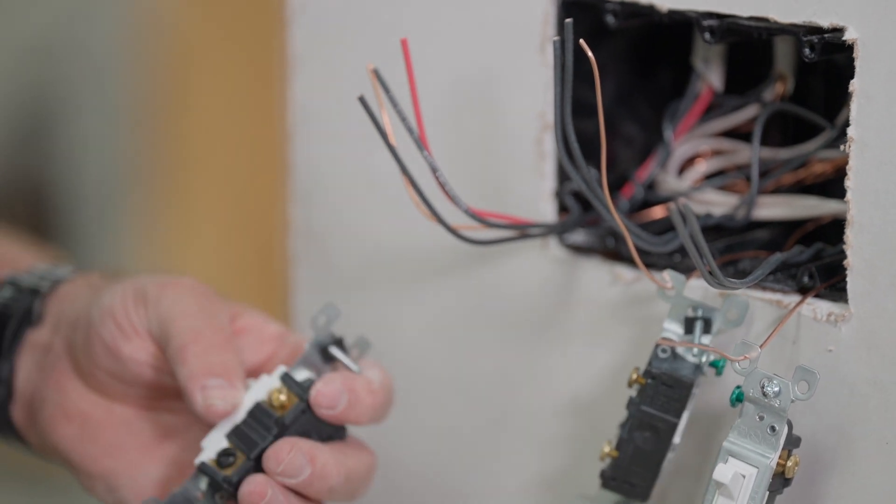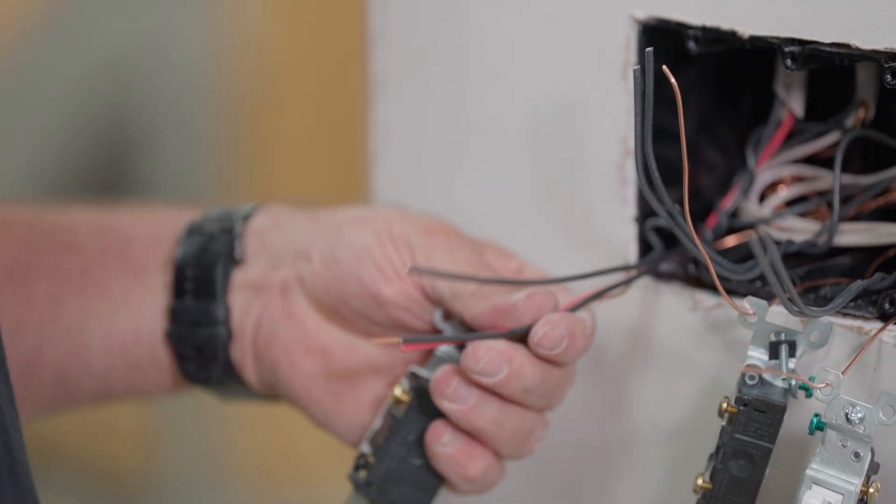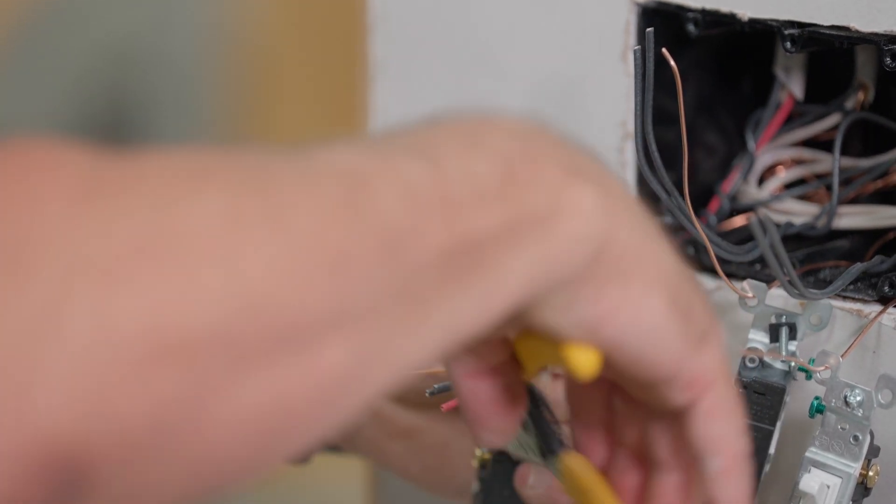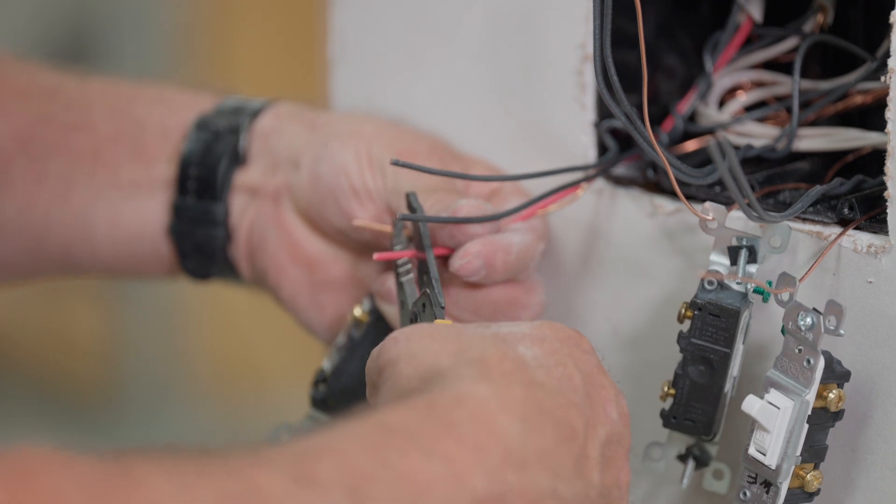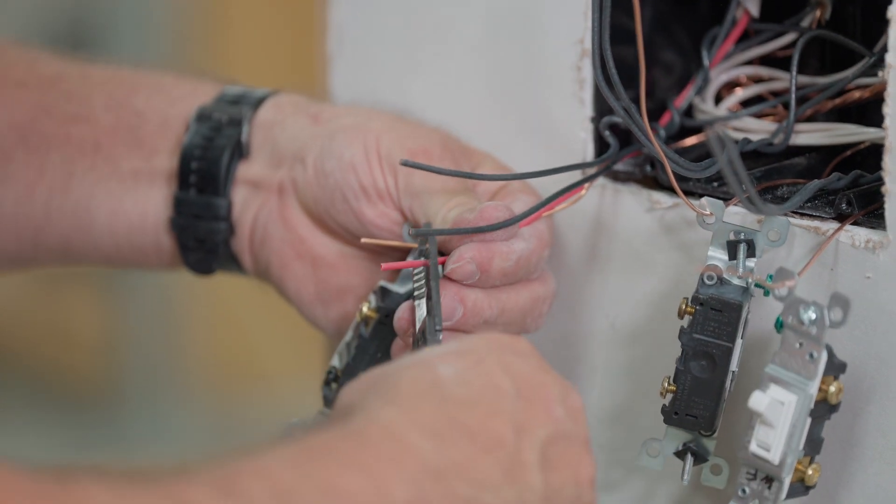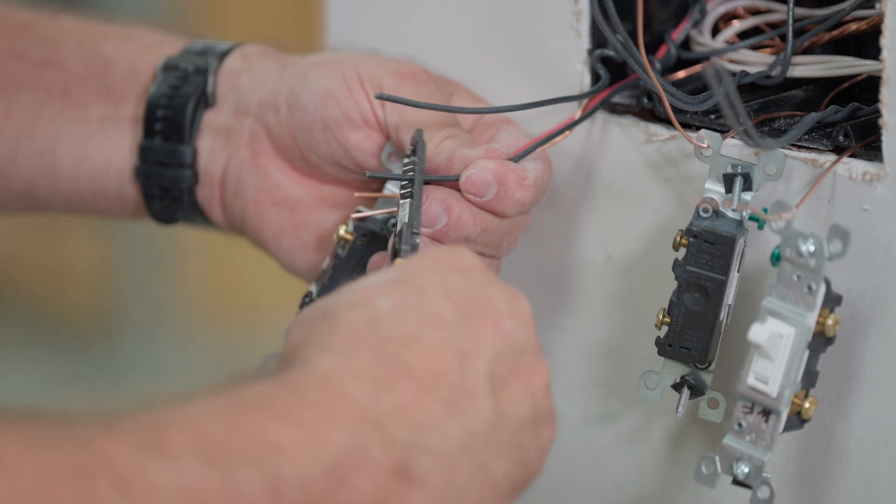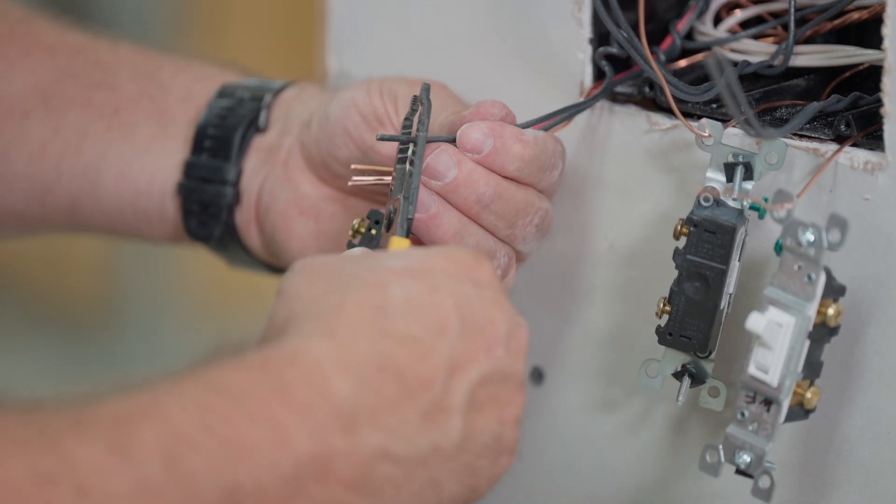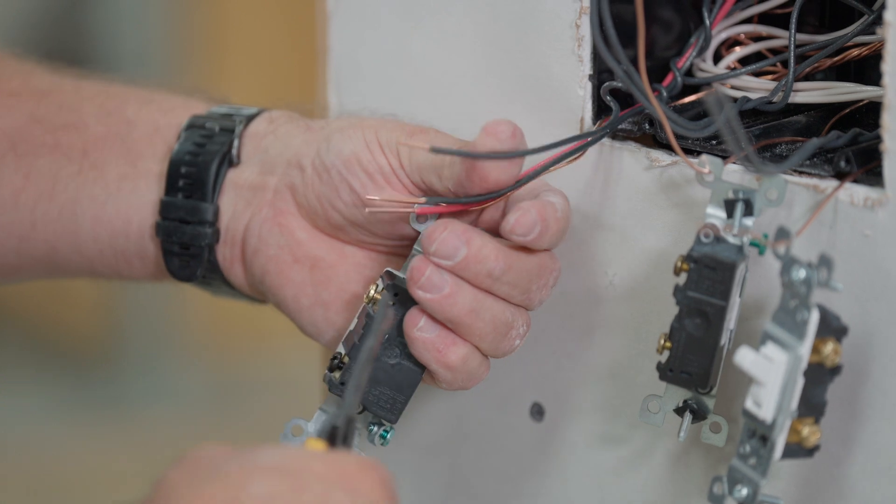So we'll take this first switch and strip these about the length that we need to. They're a little long, so I'm going to cut them a little shorter and then we're going to strip these. This is number fourteen wire so we can stab in. Remember, if it's number twelve wire, you're not allowed to use the stab-ins. It's only fourteen and below for stab-ins.